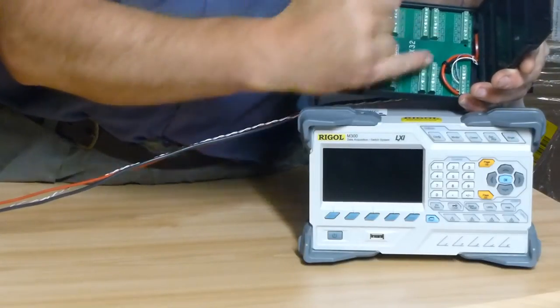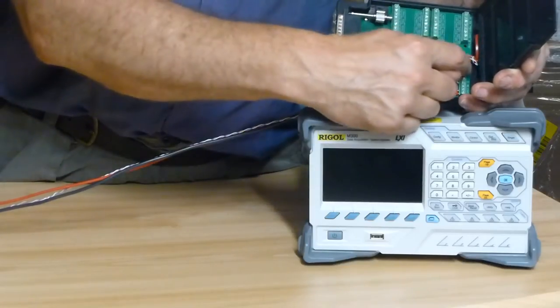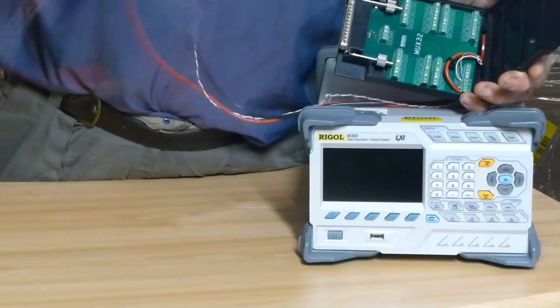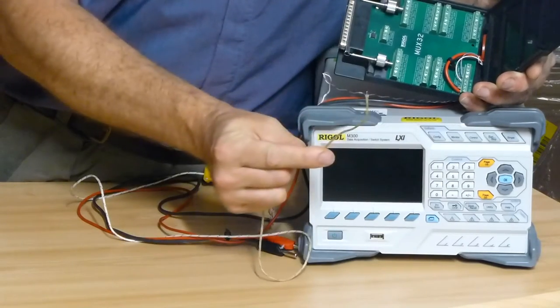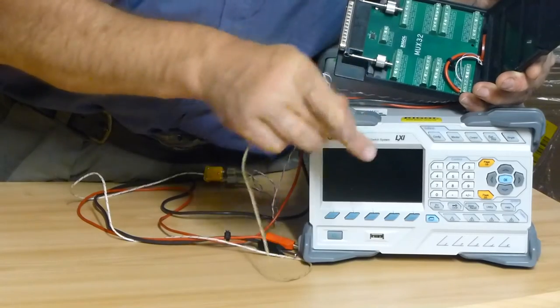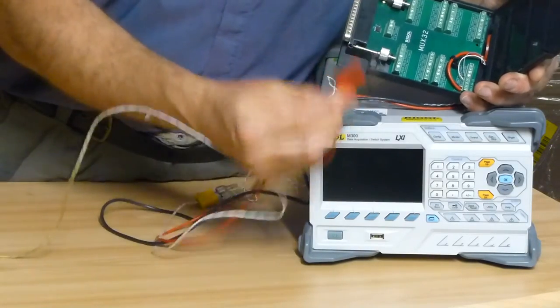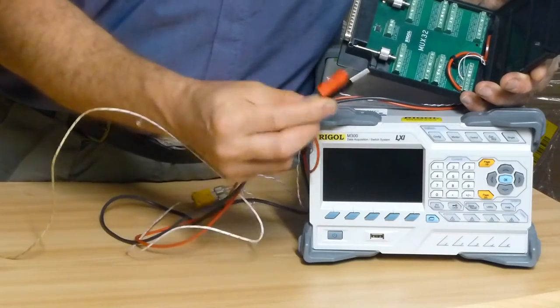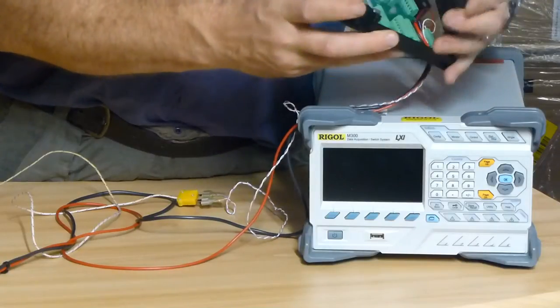You can see here that I've wired into two connections. I've wired a voltage measurement and a temperature sensor, and those two units are here. This is a thermocouple that I've wired in. It's a simple K-type thermocouple, and this is a two-wire digital multimeter connection to measure DC volts. So I'm just going to close that up so that it's nice and secure.